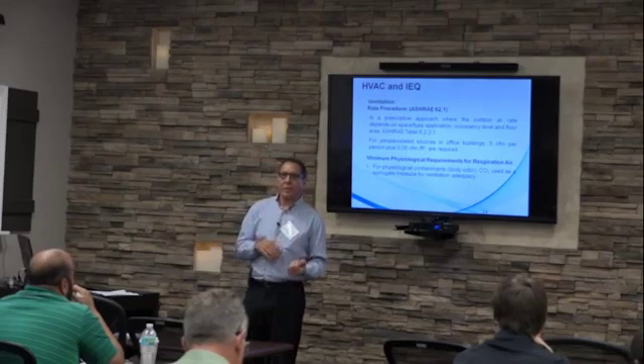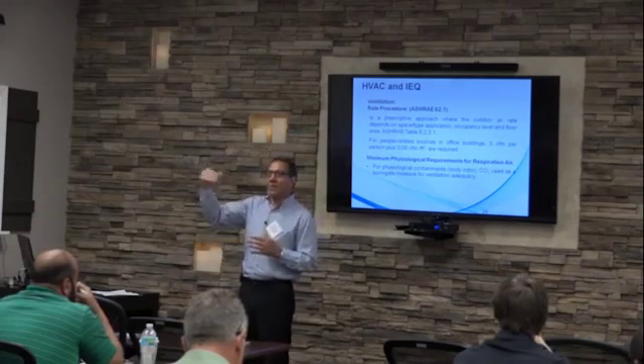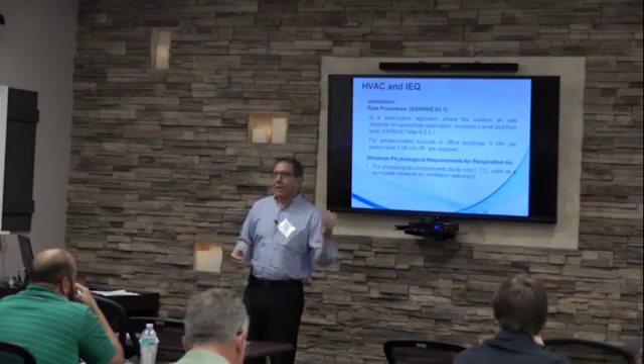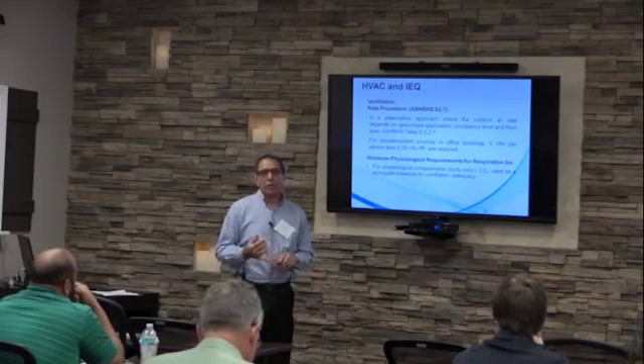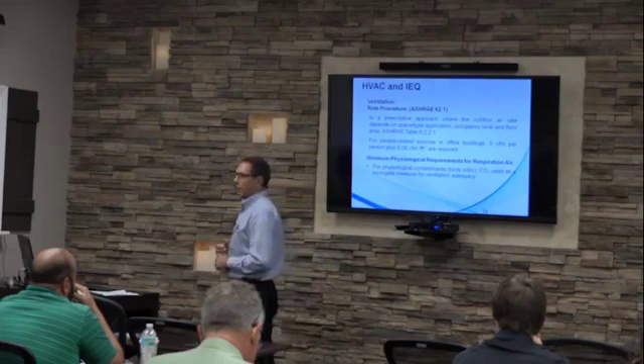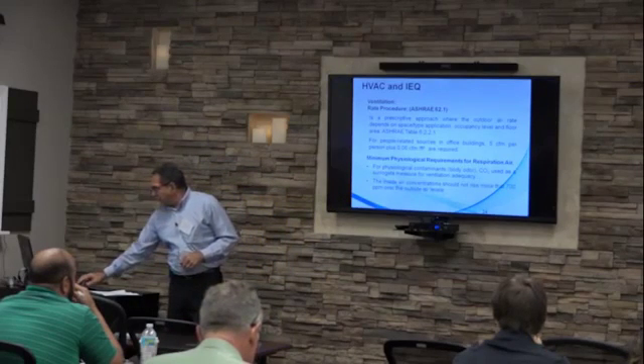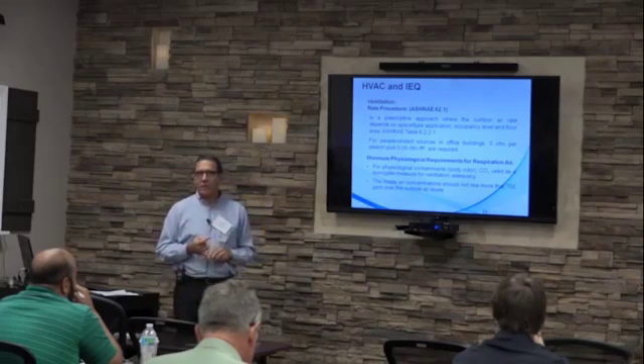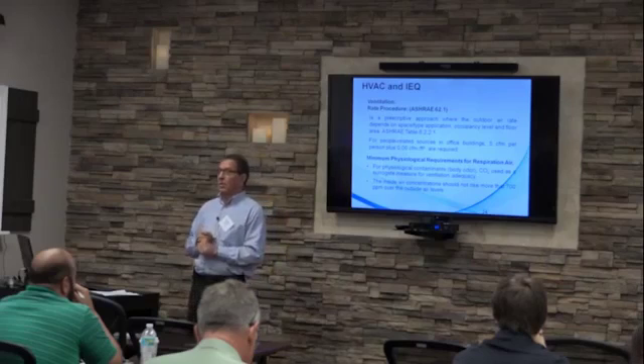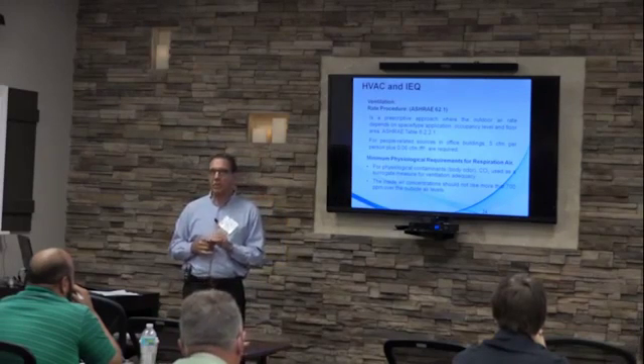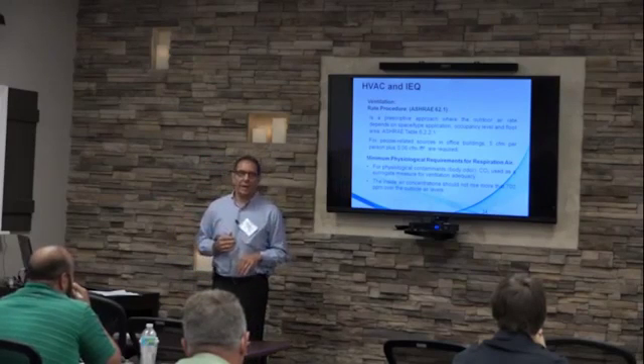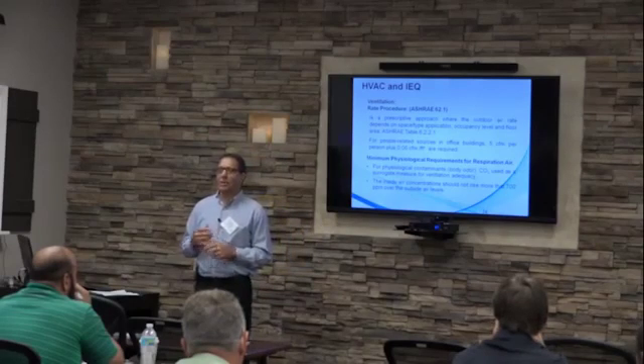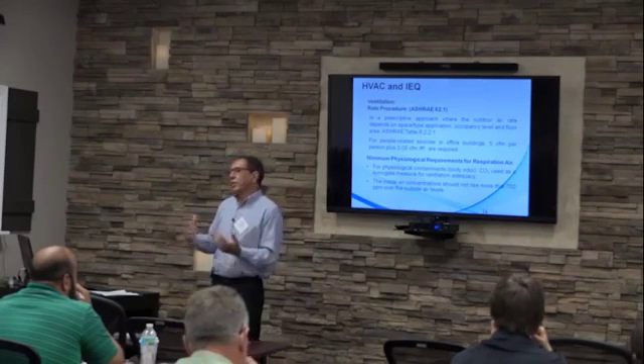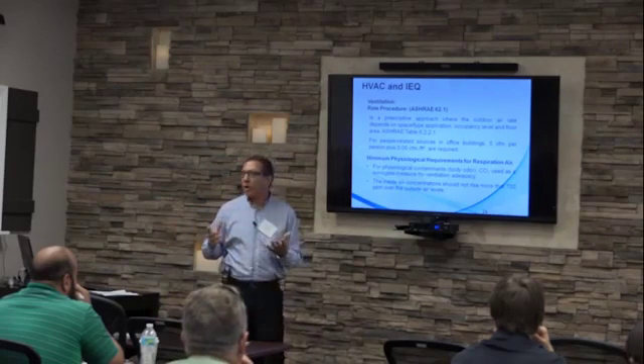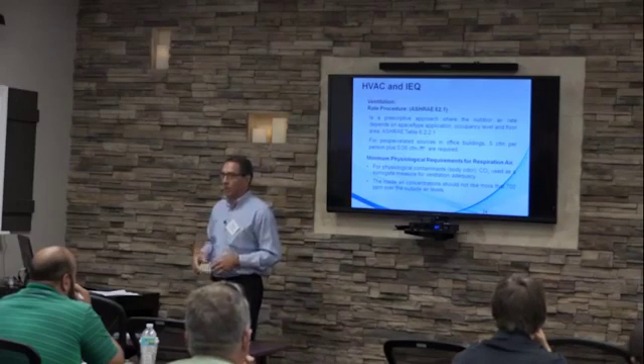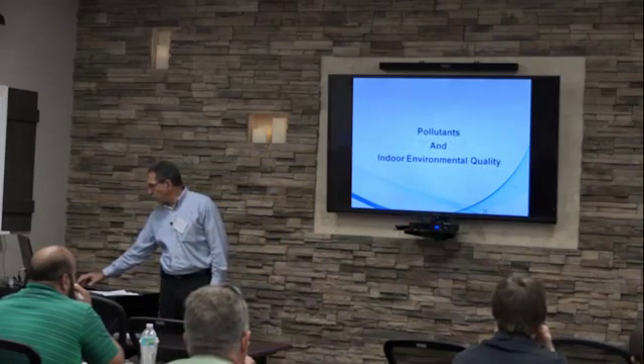As people enter the building, they're going to produce carbon dioxide. So the more people enter the building, the levels of carbon dioxide are going to increase if no ventilation is provided. So with ventilation, we can control the amount of carbon dioxide, and with that, we control the amount of bioeffluents that we generate, body odor. And so they say that if we use carbon dioxide to measure the adequacy of the ventilation system, the carbon dioxide levels inside of our building should not rise 700 parts per million over the outside air levels. Typically, the outside air contains about 300, 400, in some cases 450 parts per million. So with the 700, we see that about 1,000 to 1,200 parts per million are normal in a building that is properly ventilated.